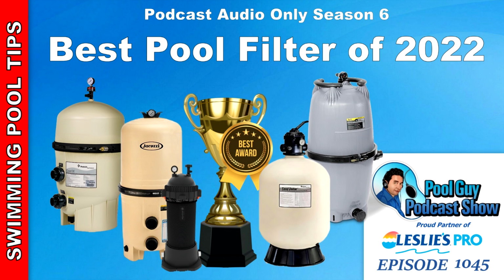Number 1 is that the sand filter doesn't need to be broken down and cleaned every 6 months, 4 to 6 months, or every month. You don't have to take the top off and take out the elements, which there are none in there, by the way. There's actually sand in there, or an alternate media to sand. So the sand filter does have the convenience factor of all you need to really do is backwash the sand filter whenever the filter pressure or PSI goes up 10 from the clean point.